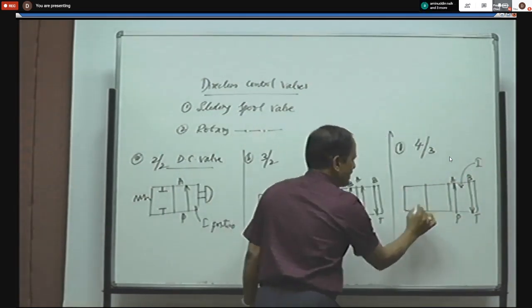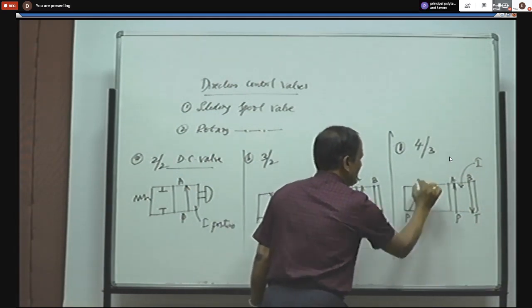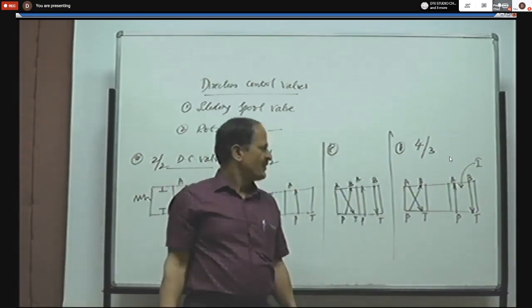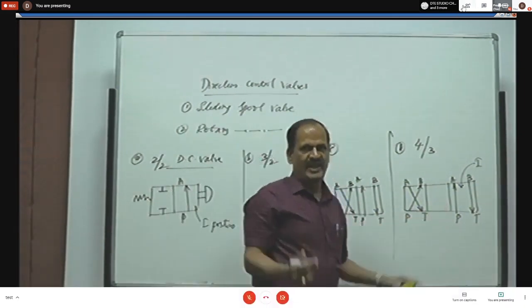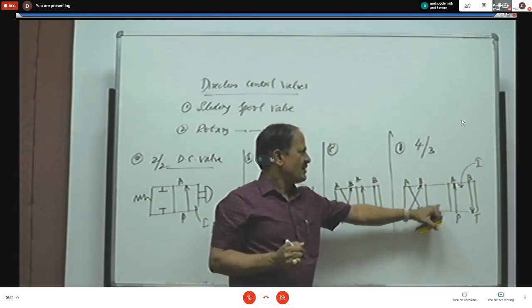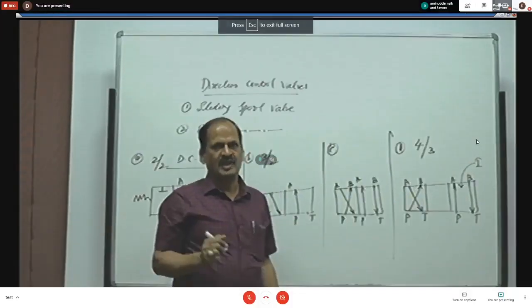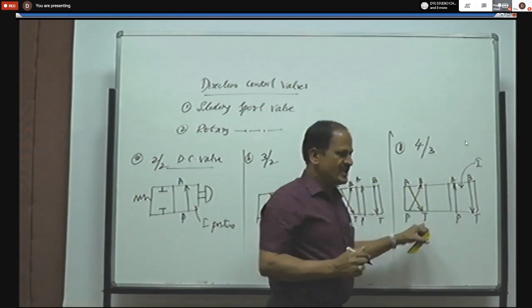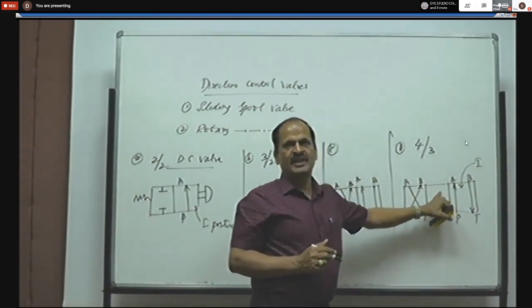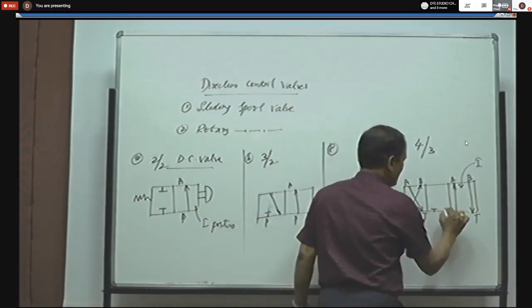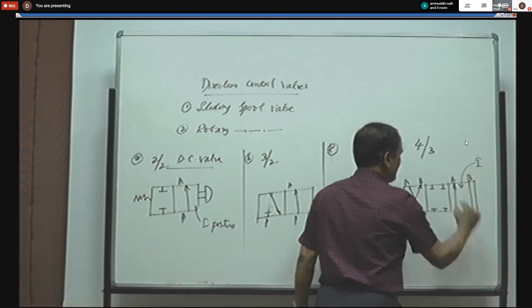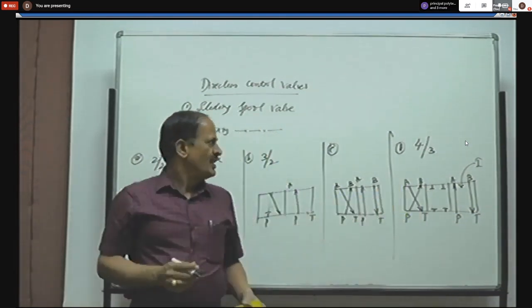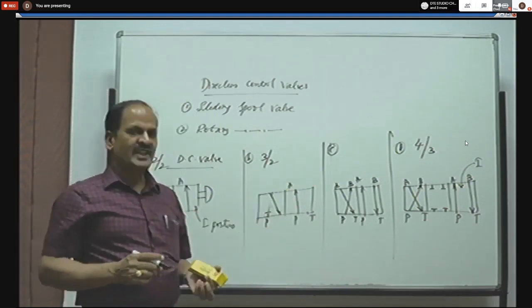In the neutral position — 4x3 DC valves are most commonly activated by a hand lever, not a push button (push button is used only for 2x2 and 3x2) — whenever the sliding spool is in neutral position, all the ports P, A, B, and T are closed and no actuators are activated. This is called the neutral position of the DC valve. The middle box always represents the neutral position. This is the symbolic representation of the 4x3 DC valve.